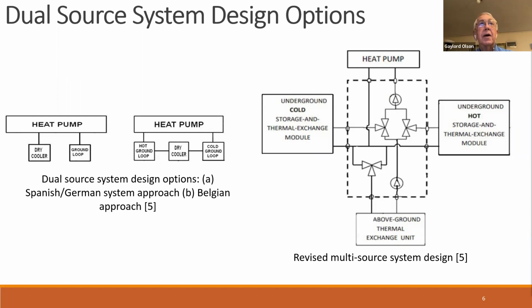So to me, logic tells me that if you can have both of these in one system, you will likely get even better than 50%. It might be a 60% reduction in the bore field size. But there will still be a need for drillers and people digging trenches, because on the coldest winter nights and the hottest summer afternoons, you still want a bore field to take care of those extremes.